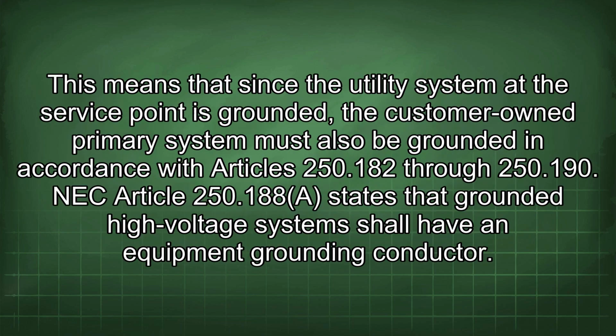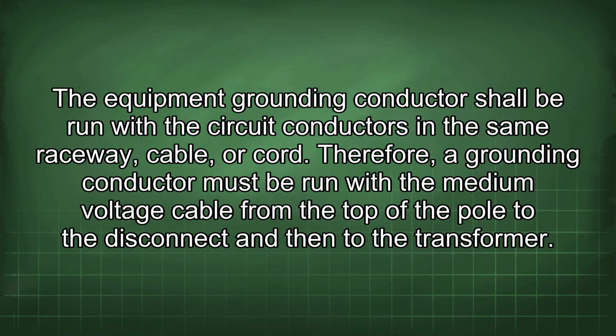This means that since the utility system at the service point is grounded, the customer-owned primary system must also be grounded in accordance with Articles 250.182 through 250.190. NEC Article 250.188 states that grounded high-voltage systems shall have an equipment grounding conductor. The equipment grounding conductor shall be run with the circuit conductors in the same raceway, cable, or cord. Therefore, a grounding conductor must be run with the medium voltage cable from the top of the pole to the disconnect and then to the transformer.